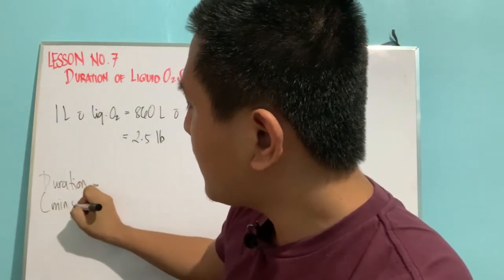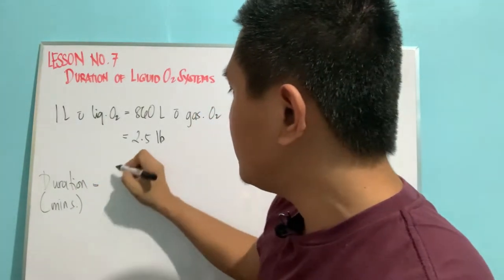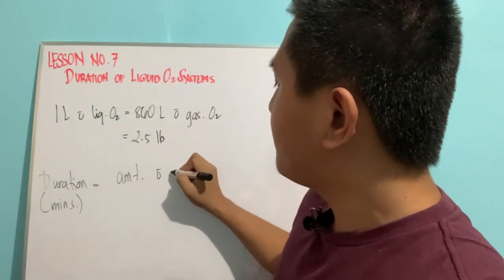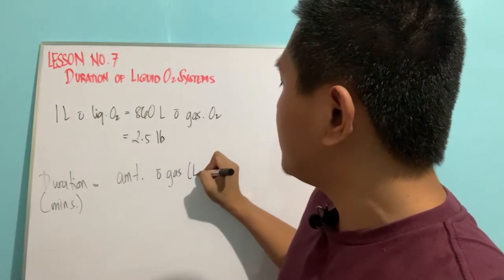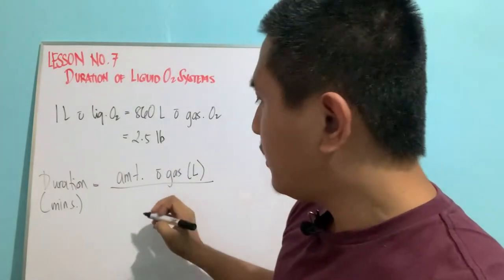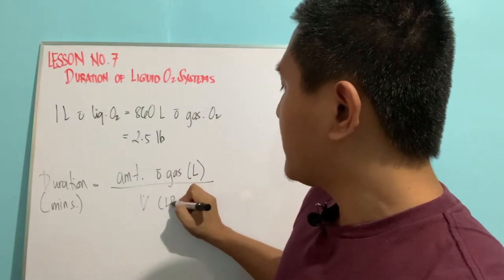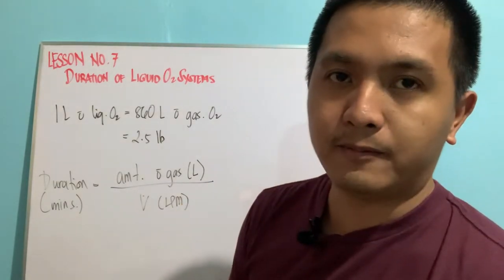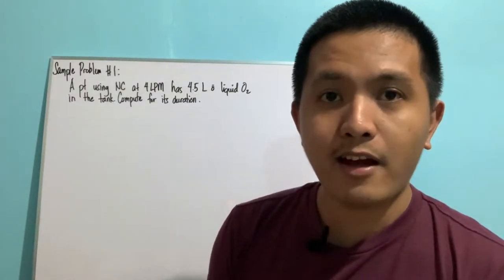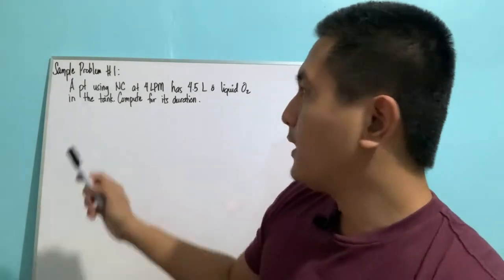The formula for computing the duration of a liquid oxygen system is expressed in minutes. Duration is equal to the amount of gas in liters divided by your flow rate, which is expressed in liters per minute.